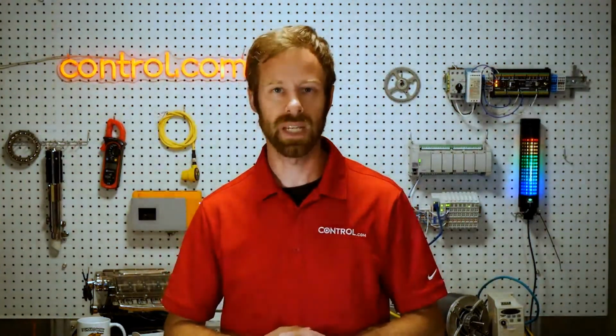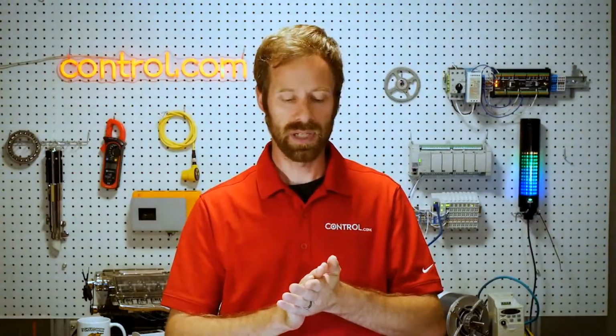So as a wrap-up summary, we looked at some of the basic I/O devices, these switches, electromechanical, which means when you push a button, you apply force, you hear a click, you feel something move. What's happening is a piece of metal touching another piece of metal, creating a switch contact, much like a light switch, and allows electricity to flow, and that provides the most basic form of input sensing for a PLC or a control system. We also looked at some of the 3-wire discrete and analog devices. These can provide a bit more information than just a mechanical switch clicking on and off. They can provide variable information that we then leave up to our programming skills to decide what we are going to do with this information.